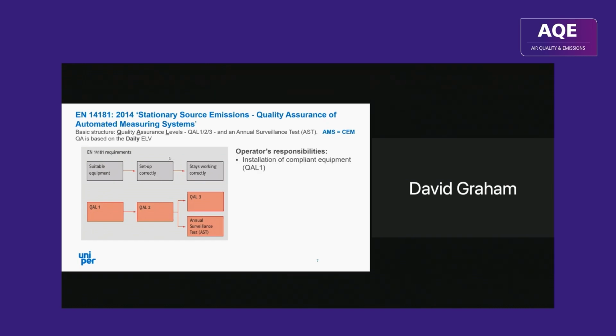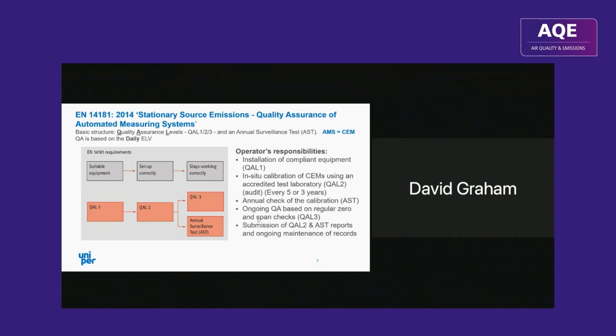So the operator needs to install compliant equipment. This requires type-approved equipment. An accredited test laboratory needs to come to site to calibrate the CEMs every 3 or 5 years. There's an annual check of that calibration, the AST, which again involves the test laboratory coming to site. And then there's ongoing QA checks performed by the operator on a regular basis, say weekly, zero and span checks. So that standard is supplemented by a few other standards in relation to dust, stack flow rate, and mercury.